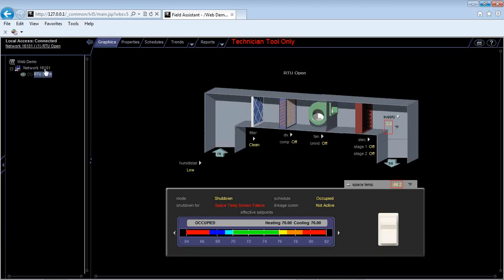If I click on this network, first off, just general basic BACnet protocol is you need to have a network, and you have a network number for your entire communication bus, which for Carrier defaults to 16101. Then you also have an address that we talked about before, which would be 01 for this one controller. So this is defaulting as network 16101. That's only on the Carrier side. If you're wiring this into, let's say, an ALC network, they're going to have a different network number. It's not that big of a deal, but you should always see 16101 or 16 and then some other numbers if you're viewing it on Field Assistant.